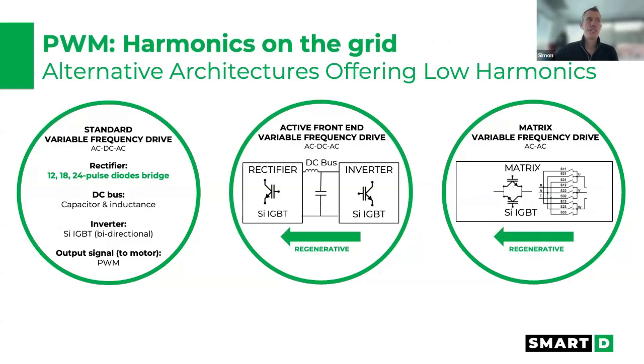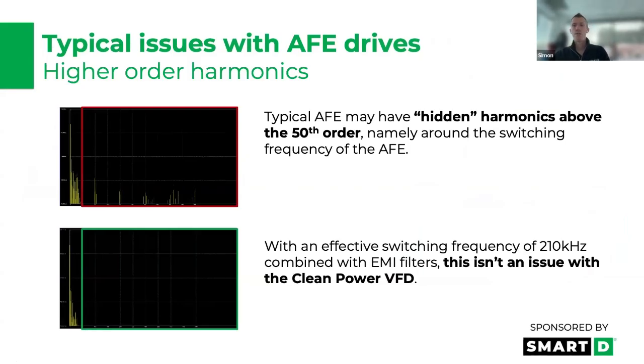Let's first talk about the active front end. Typically, in an active front end drive, they are focusing only on the first 50 orders of harmonics. So this is the portion on the left of that red line. But everything on the right, beyond the 50th order, is ignored by an active front end, because there's this kind of blind spot between the EMI zone and the harmonic zone that is not regulated. So that's where you'll typically see manufacturers hide those higher order harmonics, and you can clearly see them in this signature of a leading active front end. In contrast, with the clean power VFD, not only can you see even visually that your harmonic content is lower for the first 50 orders, but you don't have that blind spot of hidden harmonics. So this already is an advantage of our drive compared to other active front ends.